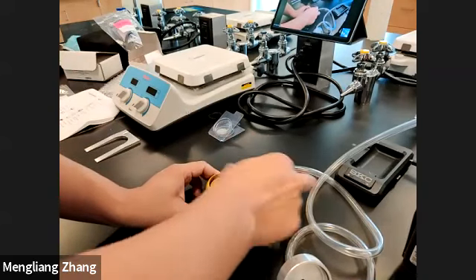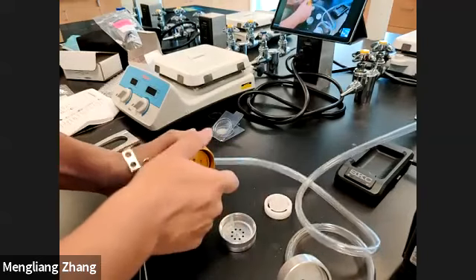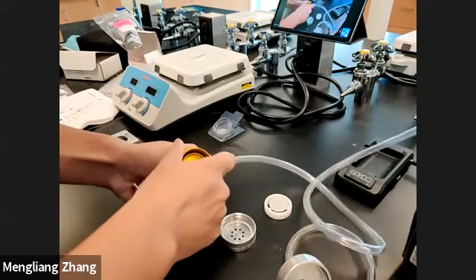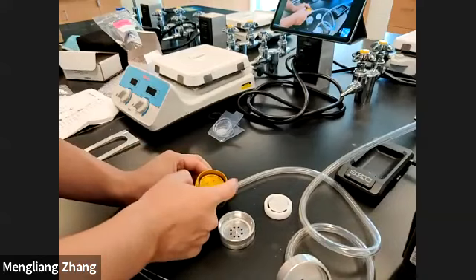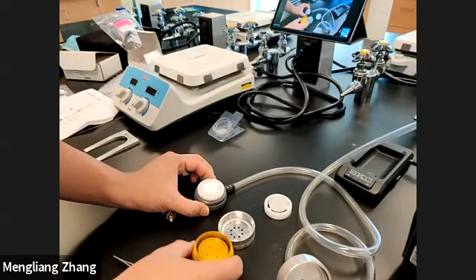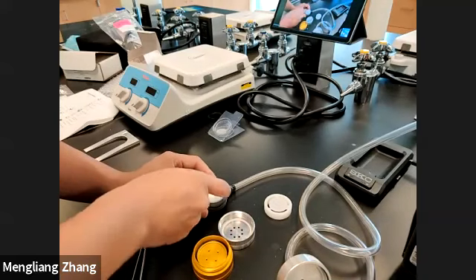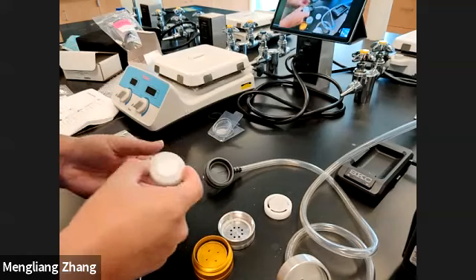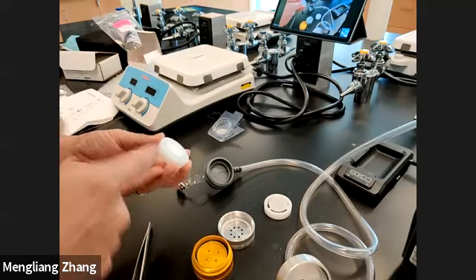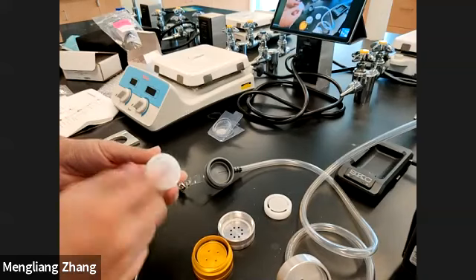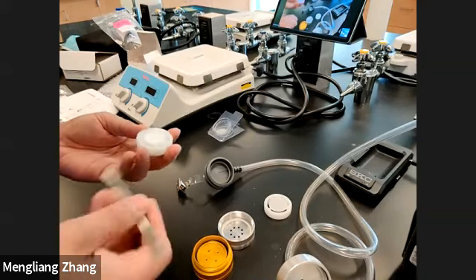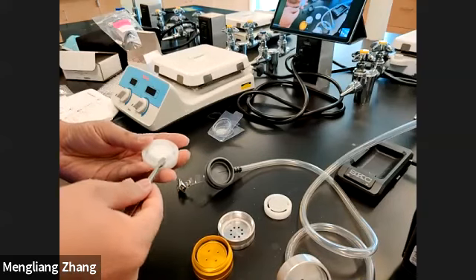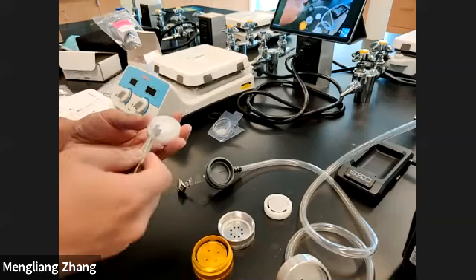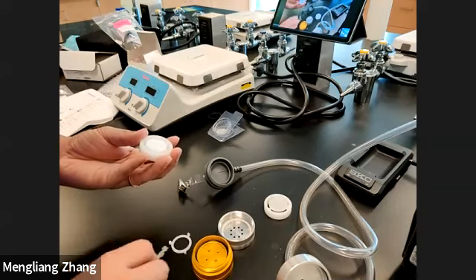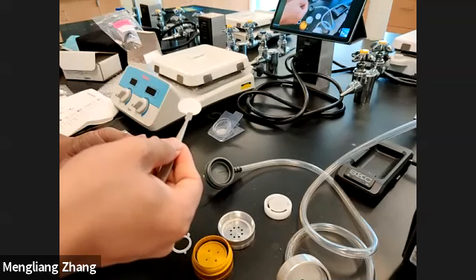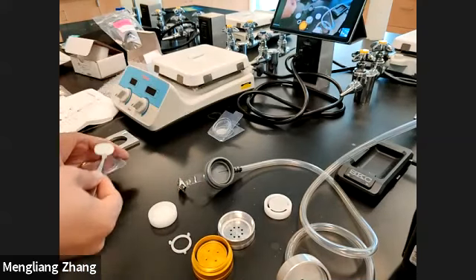And then you need to remove the top cassette and also unscrew the PM 2.5 inlet. Unscrew this and put it on the side. Then you have the second cassette here, and take it out. We have 2 different filters in this cassette. First we remove the 2.5 filter, which is on the top. So we need to remove this cassette or filter retainer. You just use tweezers to remove it, put it on the table, and take out the filter and put that into another filter keeper.